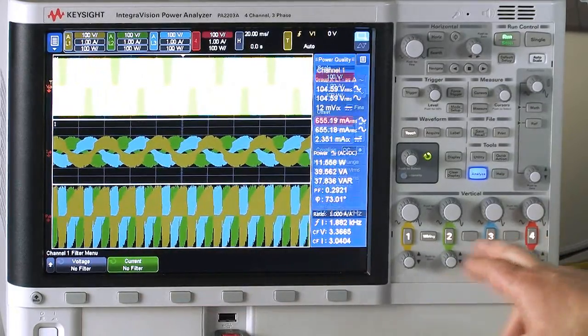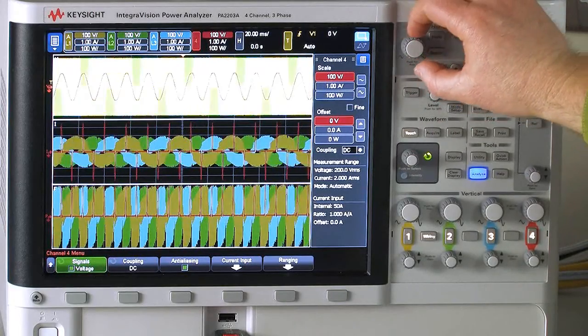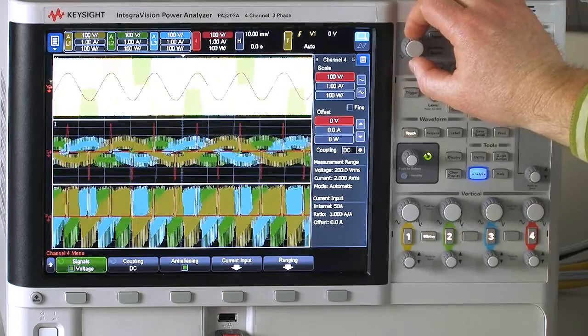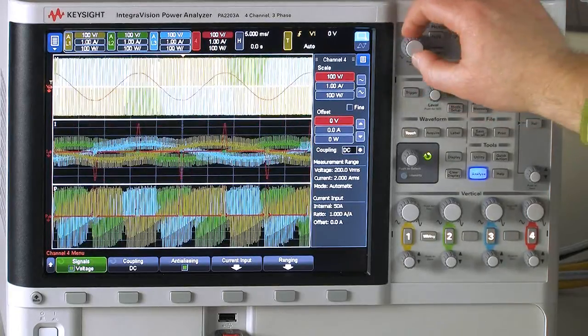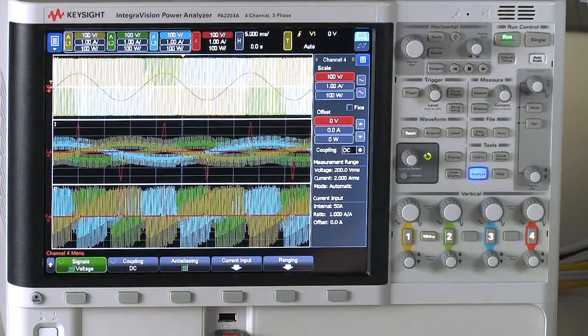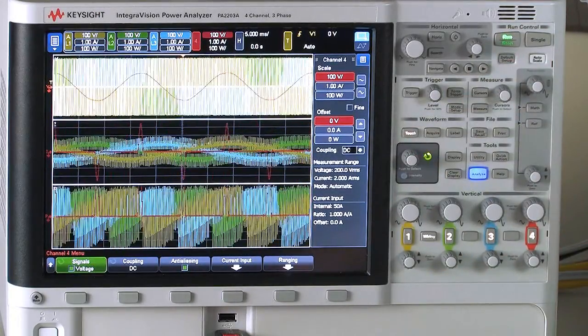And I can turn on channel four here and that's actually my sine wave input. That's the 60 hertz, 120 volt line in. And you can see it's actually being rectified. You can see the first thing it does is go directly into a rectifier based on that current pulse. That's probably what's happening inside the device. There's no power factor correction.